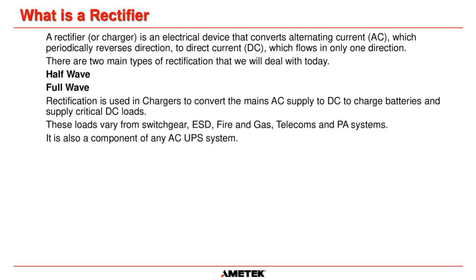It's used to convert AC to DC to charge batteries and supply critical DC loads. Those loads can vary from switchgear, tripping and closing springs, logic circuits, ESD (emergency shutdown circuits), fire and gas, telecoms, PA systems, and many more. It's also a component of any complete AC UPS system, because you have to convert the AC into DC, and then that DC has to be converted back into AC to feed your critical AC loads.